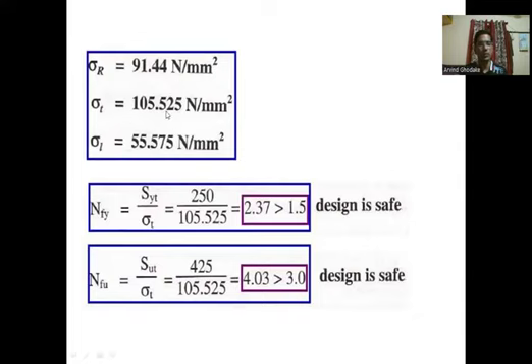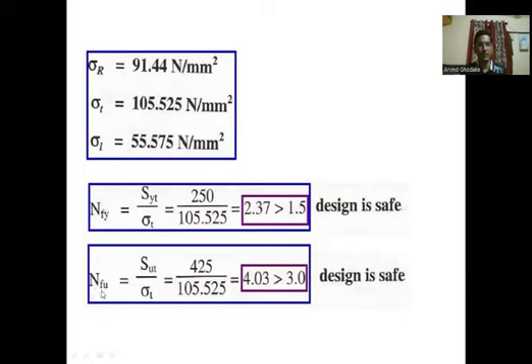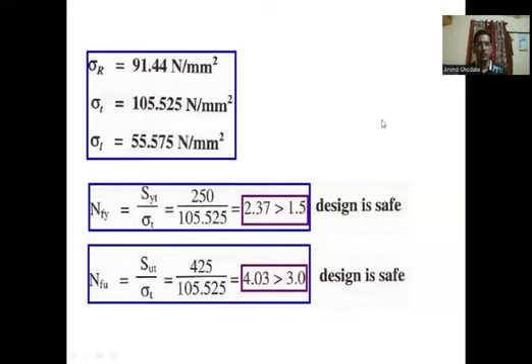Summary of results: circumferential stress = 105.525 N/mm², longitudinal stress = 55.575 N/mm², resultant stress = 91.44 N/mm². Factor of safety based on yield: FOS_Y = SYT / sigma_T = 250 / 105.525 = 2.37 > 1.5, so design is safe. Factor of safety based on ultimate: FOS_U = SUT / sigma_T = 425 / 105.525 = 4.03 > 3, so design is safe. This is how we solve problems on unfired pressure vessels to calculate circumferential, longitudinal, and resultant stresses and assess design safety.